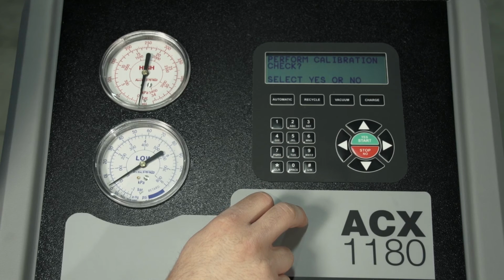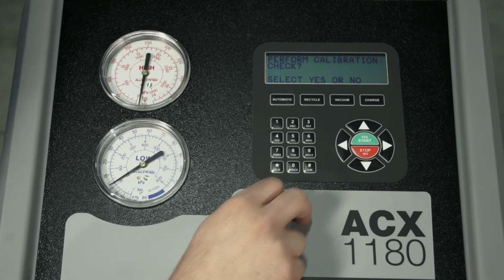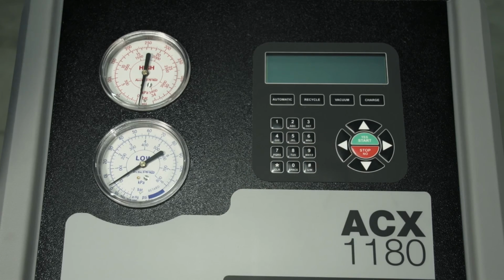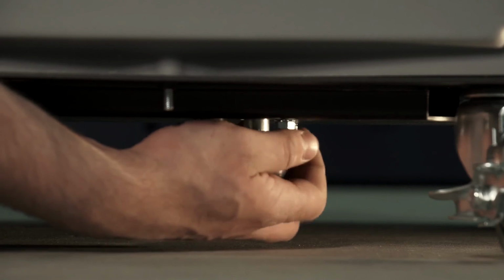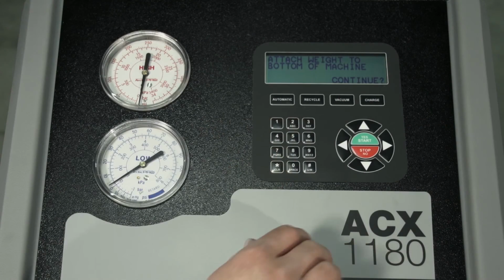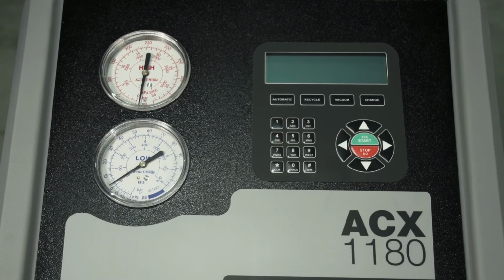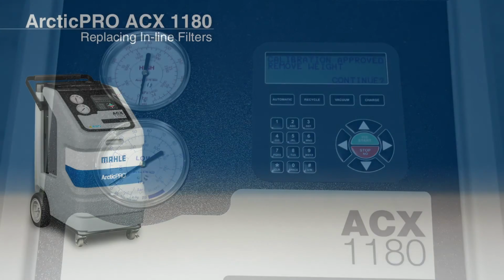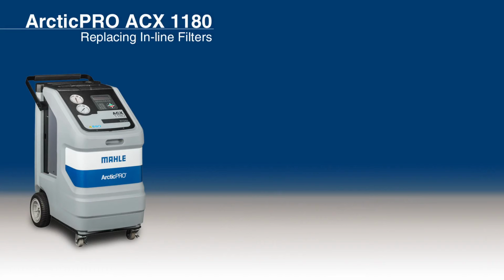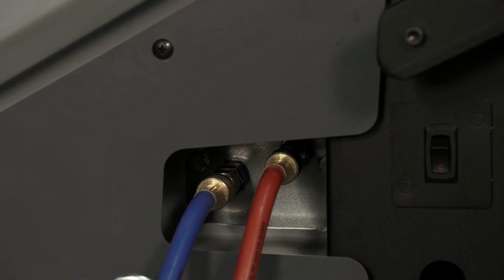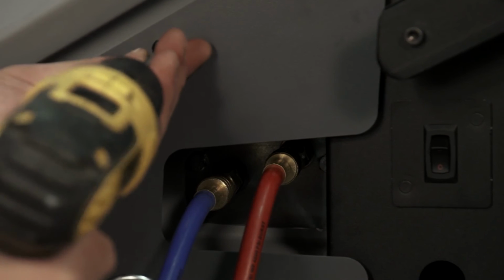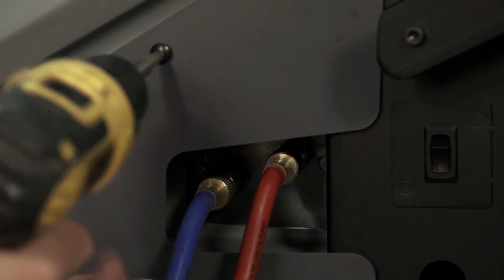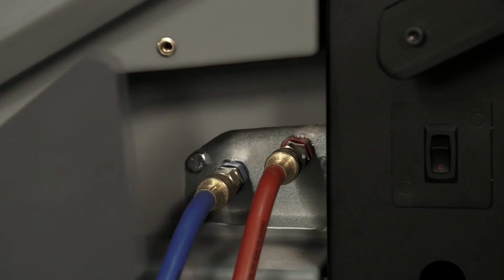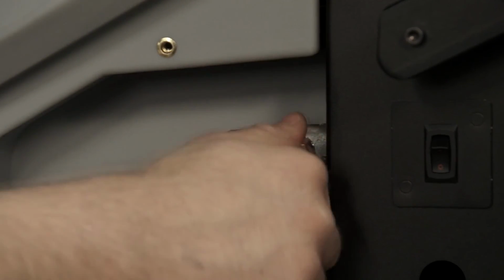The screen will display Perform Calibration Check. Press Yes again. When prompted, attach the weight to the magnetic post on the bottom of the machine. Press Yes to continue. After the calibration is approved, remove the weight. Replacing inline filters. The inline filters must always be changed when replacing the filter dryer. First, drain the service hoses, then remove the access panel. Disconnect the service hoses from the inline filters.